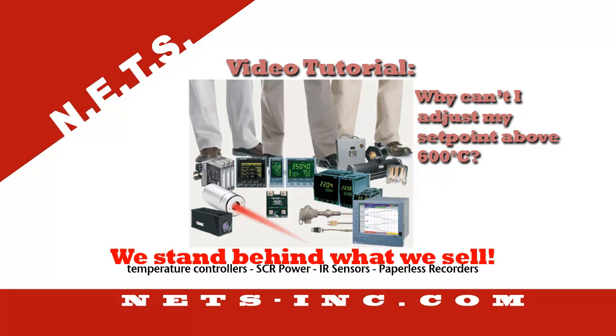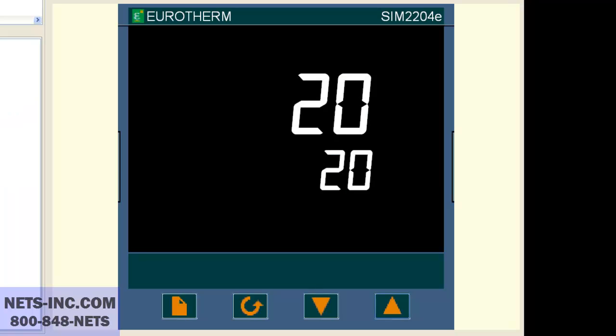I cannot adjust my set point above 600 degrees C — what could be the problem? This video tutorial will show you how to change the set point number one high limit so that a set point value of 600 degrees C can be entered on a Eurotherm 2200 series controller. The two typical reasons why this can happen are either the range high value is set at 600 degrees and/or the set point high limit value is set at 600 degrees.